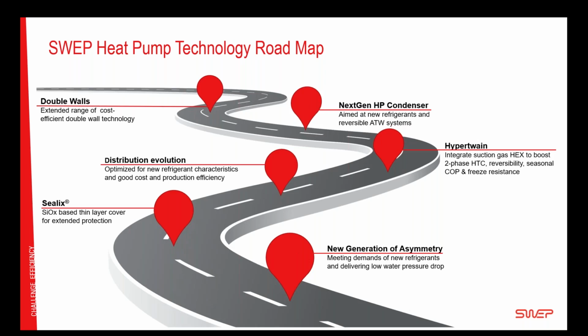The next one is Hypertwain. That is a new groundbreaking technology where we integrate a suction gas heat exchanger into the normal heat exchanger, basically to boost the heat transfer coefficient in two-phase applications. You get the most advantage when you are doing reversibility modes and focusing on seasonal efficiency, where many of the COP ratings are focusing more and more, and you will improve the freezing resistance. With a normal heat exchanger, you often need to utilize 30% of your heat transfer area to manage the superheat. With this new technology, where we integrate the suction gas heat exchanger into the heat exchanger, you only need to utilize 5% of the surface to manage the superheat that you need.